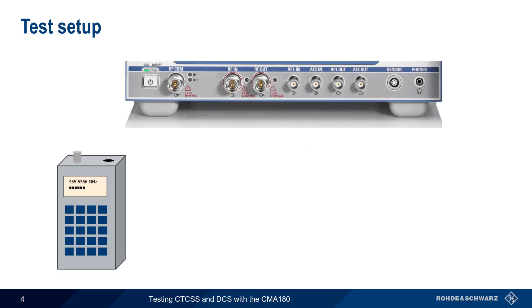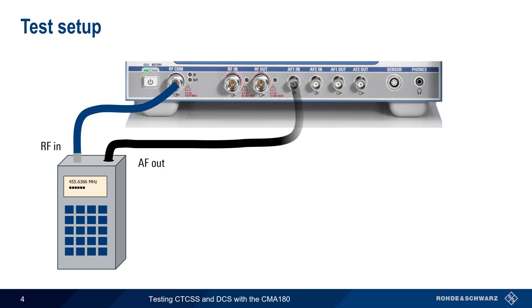Depending on our test type, we have to make either one or two connections from our radio to the CMA180. Both transmit and receive tests require a connection between RF-COM and the antenna connector on the radio — this connection carries the modulated RF signal. The second connection is from the audio out of the radio to AF1 in on the CMA180, and is only required for receive tests, carrying the demodulated audio signal from the radio back into the CMA180 for analysis.